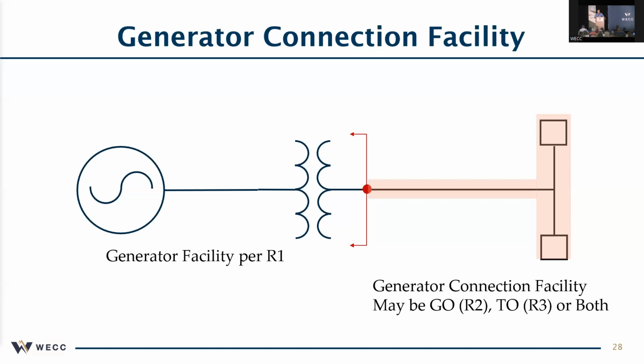And we're auditing the generator at this time. We're not auditing the TO, so we can't go call the TO and check and see. So the auditors, if they want a comfortable feeling of reliability, that these ratings are done correctly, they need that information.